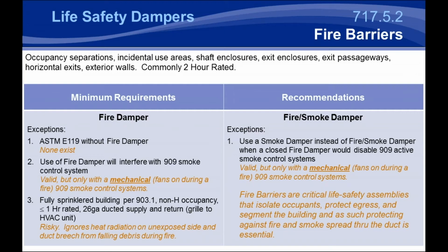So if a fire damper shuts and stops air from flowing through ductwork, it really can't interfere with a passive type containment smoke control system. Now, this is a valid trade-off for a 909 smoke control system, but typically what we see for fire barriers in a lot of cases is there will be a smoke requirement as well. And any smoke damper that's required for a 909 smoke control system needs to be tied into that system, and there needs to be positive identification if that damper is open or closed.